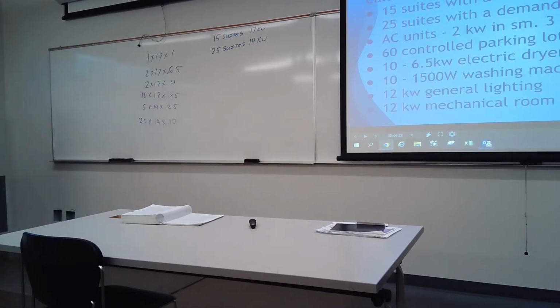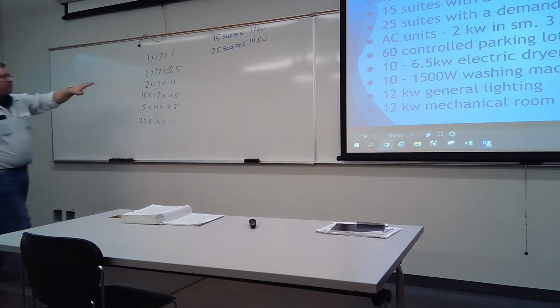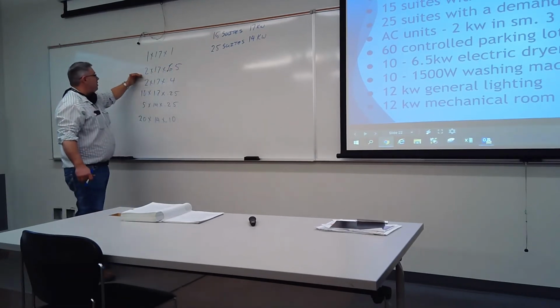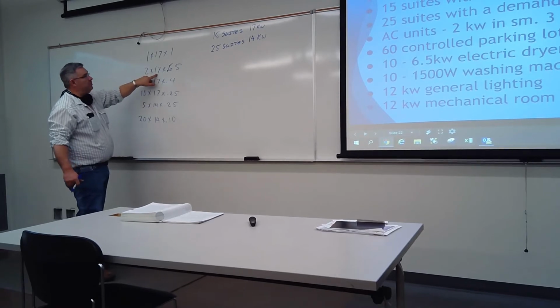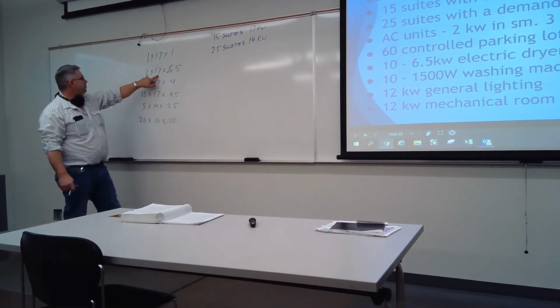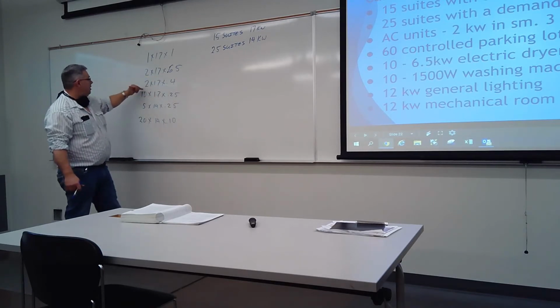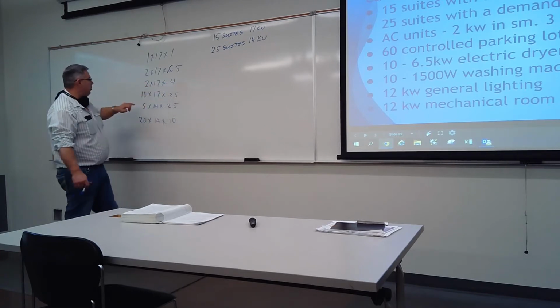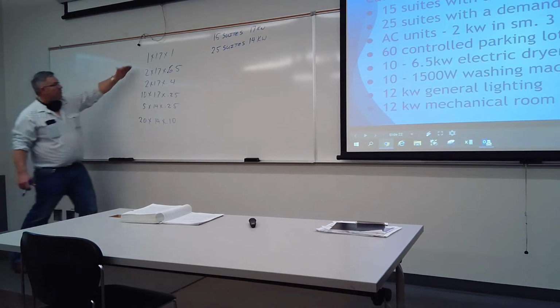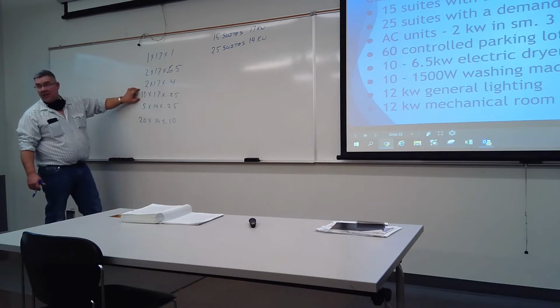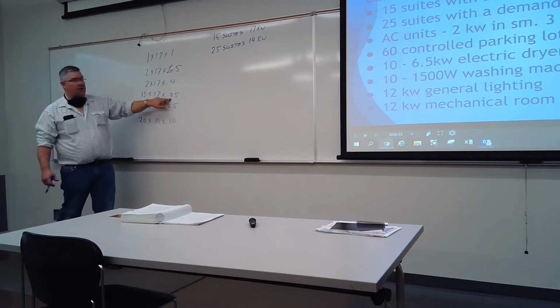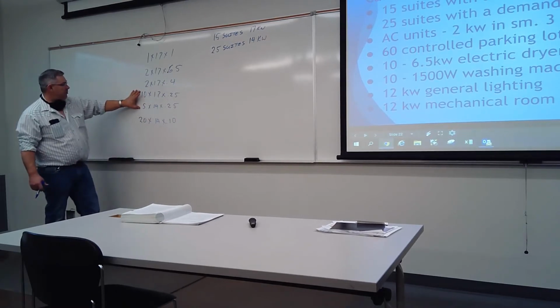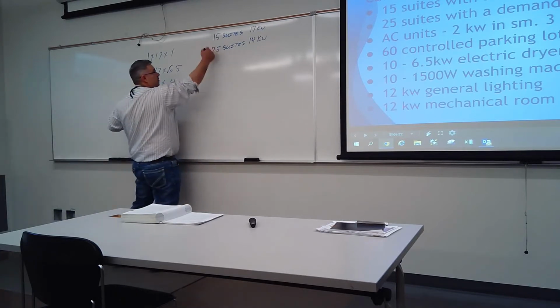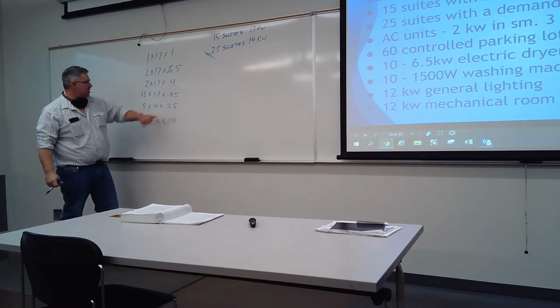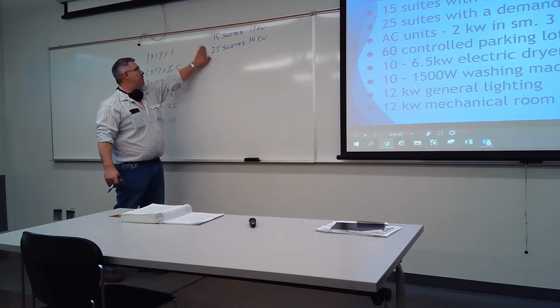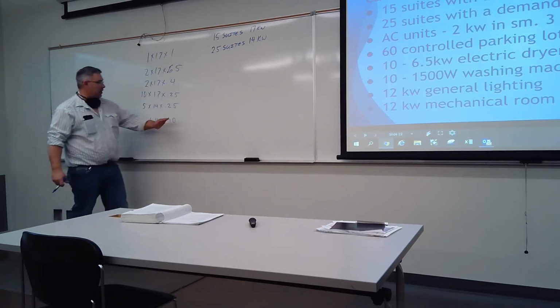Okay, so our calculation will look like this. 100% of the largest suite, which is going to be one of these ones that has a 17 kilowatt demand. 65% of the next two largest, so we had a total of 15 here, so take 2 times 17 times 0.65, 40% of the next two, 2 times 17 times 0.4, and then 25% of the next 15. Well, we've allowed for 5. There was 15 in total, so that's 10 left over, times the 17 kilowatts times 25%. To make this group of 15, we're going to need 5 out of this batch, so 5 times 14 kilowatts times 25%, and then everything else is at 10%. So there's still 20 of the suites left over, so 20 times 14 times 0.1.